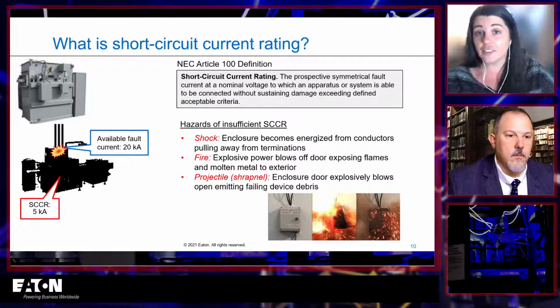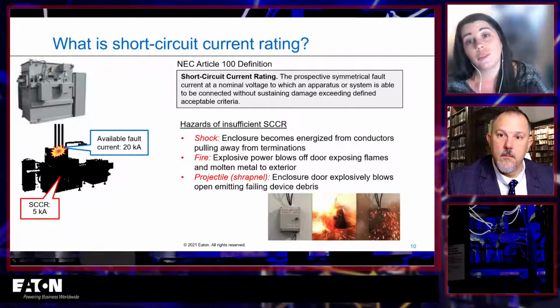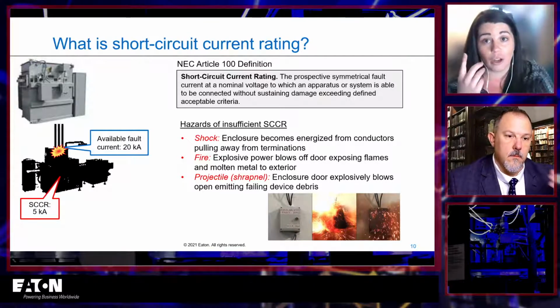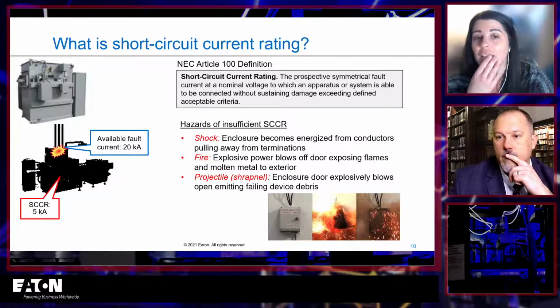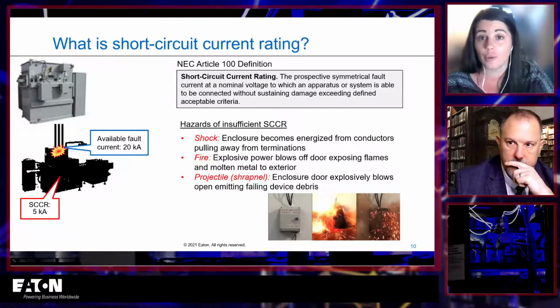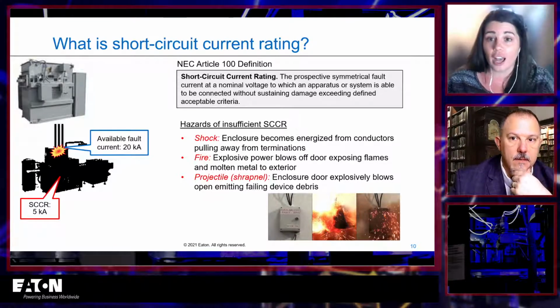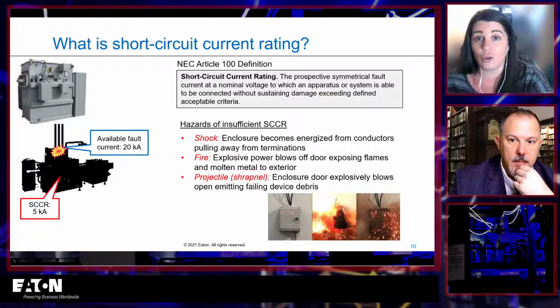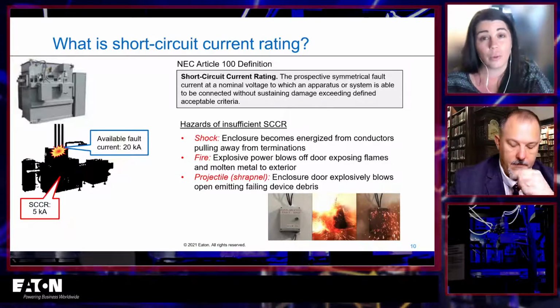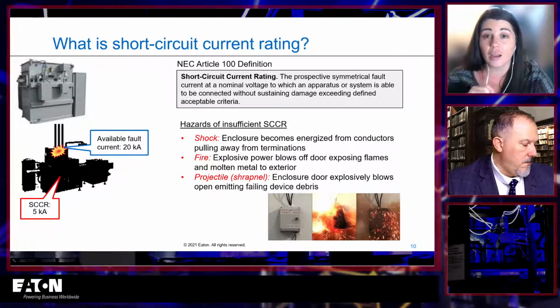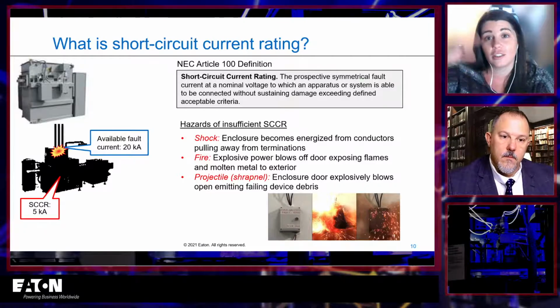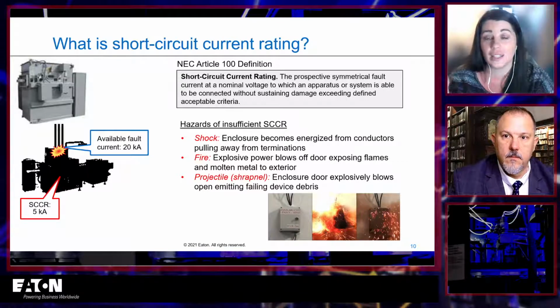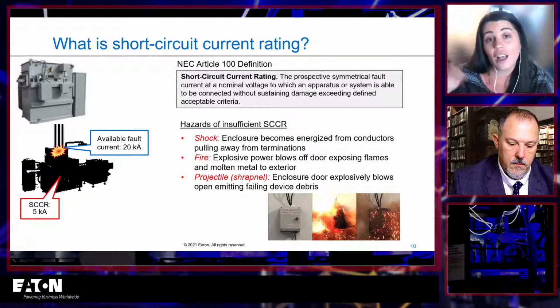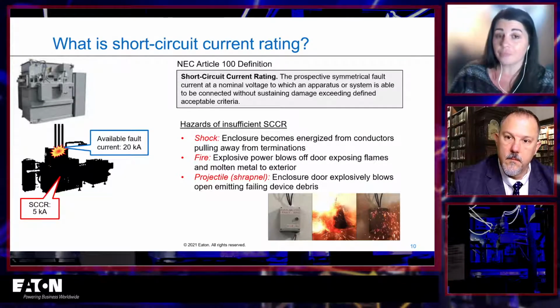When I don't have sufficient SCCR, I'm going to create one or more of these three hazards: a shock, fire, or projectile hazard. So the shock hazard is typically a result of conductors pulling away from their terminations. If the conductors pull away from your terminations, you've got live wires flying all over the place. That's not good. That's a shock hazard. And they could also possibly energize the enclosure, another shock hazard.